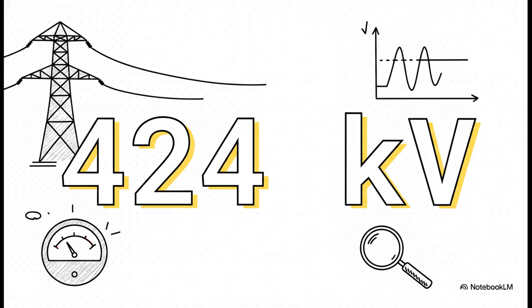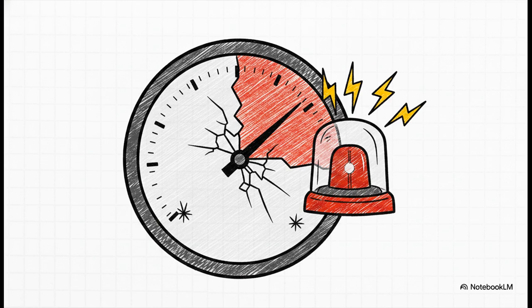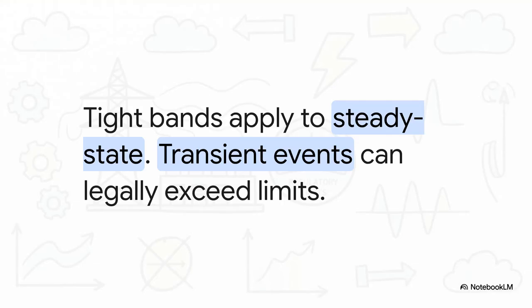Say you get a voltmeter reading of exactly 424 kilovolts on a 400 kilovolt nominal line. Based on the rules, is that compliant? No way. Absolutely not. The plus or minus 5% band tops out at exactly 420 kilovolts, so 424 kilovolts is a definitive legal violation. But keep this vital caveat in mind. These really tight percentages only apply to steady-state limits. Transient events, like a sudden switching surge, have their own much wider tolerance bands.